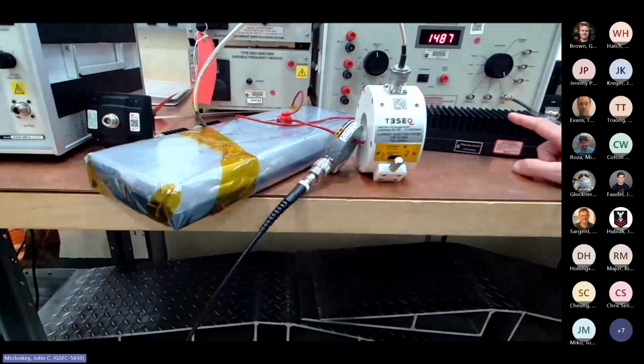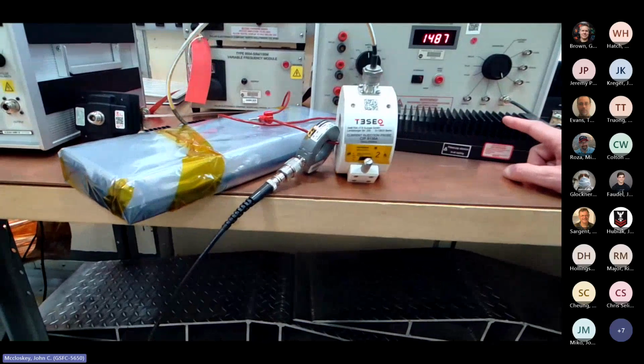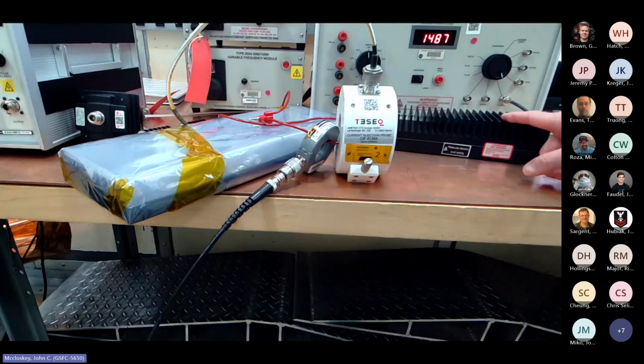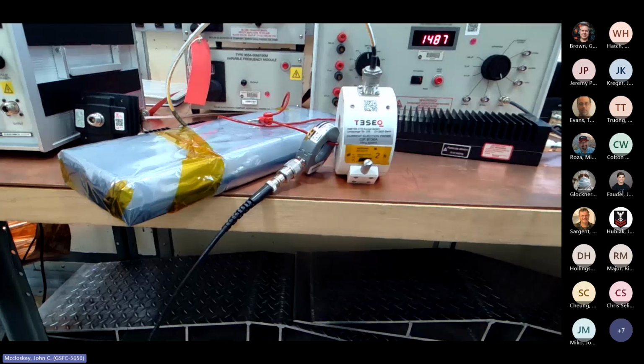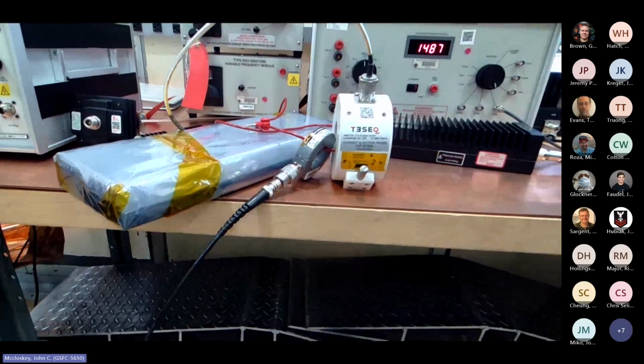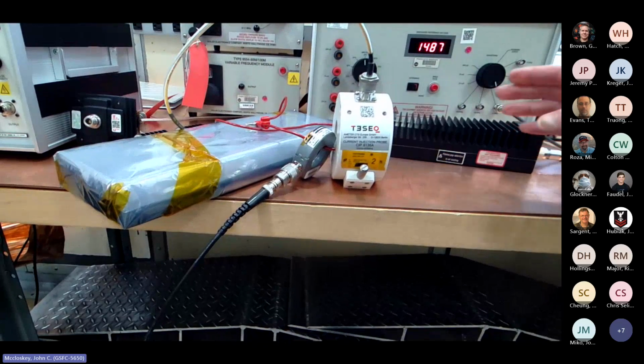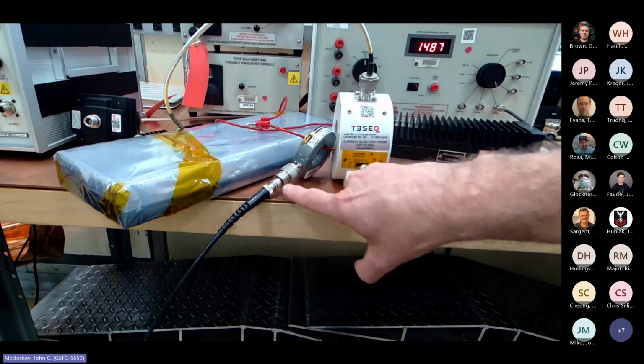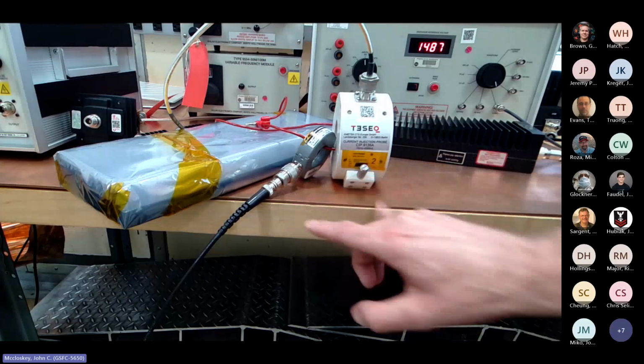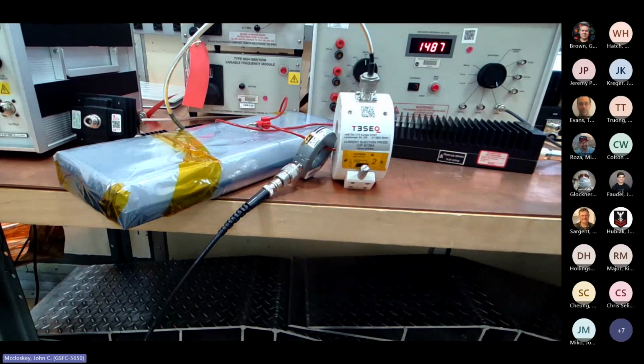So that primary attenuation, and the attenuation that's still in, is to get the drive signal so that you can drive the amplifier near the higher end of its range where it's most stable. But then the other place where you might need attenuation is at the output of your current probe, if the signal you're trying to measure is more than the range of your scope.